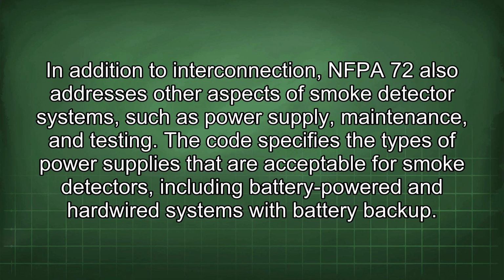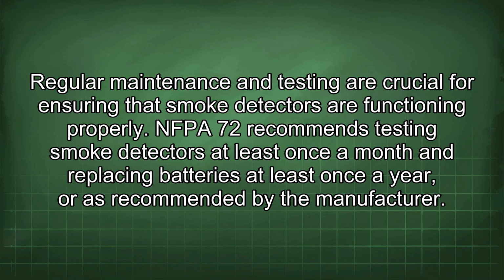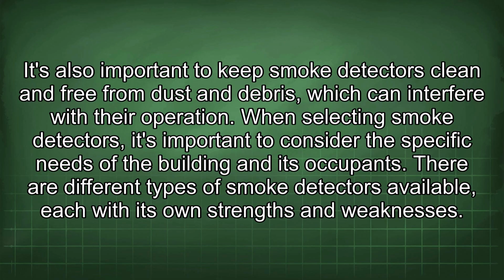In addition to interconnection, NFPA 72 also addresses other aspects of smoke detector systems, such as power supply, maintenance, and testing. The code specifies the types of power supplies that are acceptable for smoke detectors, including battery-powered and hardwired systems with battery backup. Regular maintenance and testing are crucial for ensuring that smoke detectors are functioning properly. NFPA 72 recommends testing smoke detectors at least once a month and replacing batteries at least once a year, or as recommended by the manufacturer. It's also important to keep smoke detectors clean and free from dust and debris, which can interfere with their operation.